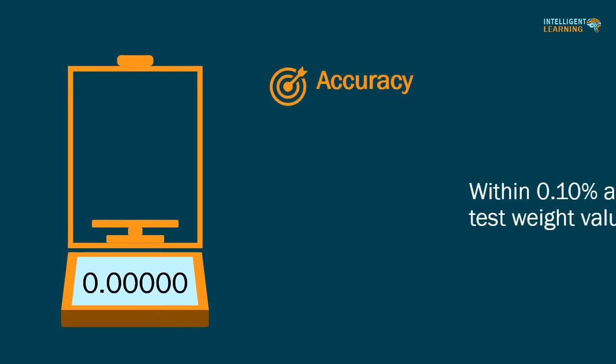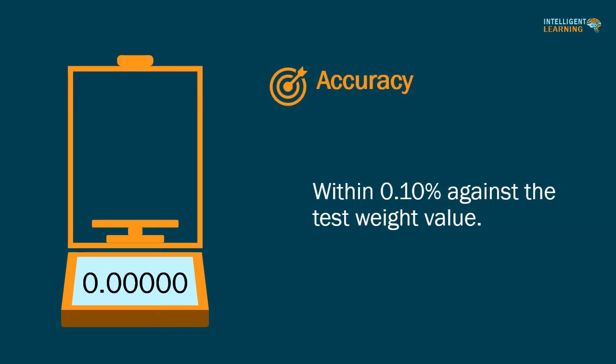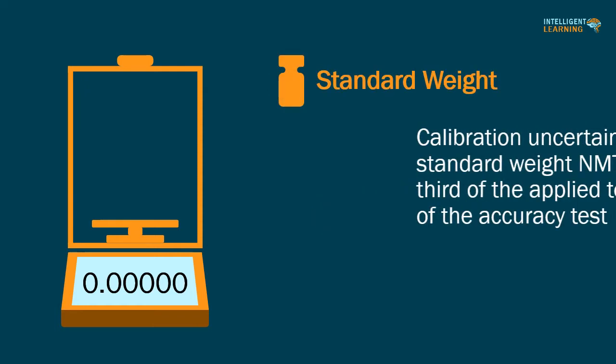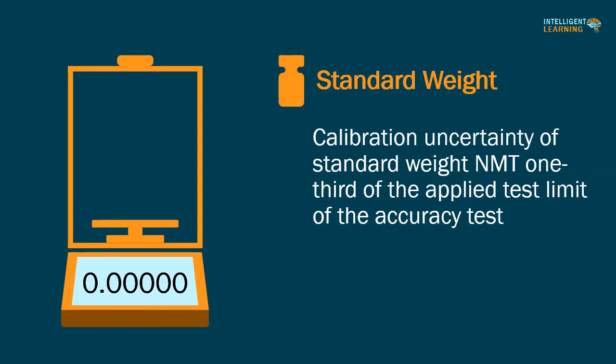The accuracy of the balance should be within 0.10% against the test weight value. The standard weight's maximum permissible error, or alternatively its calibration uncertainty, shall be not more than one-third of the applied test limit of the accuracy test.